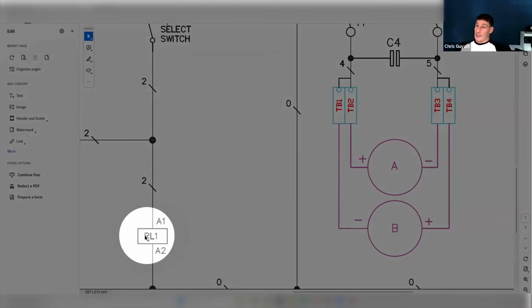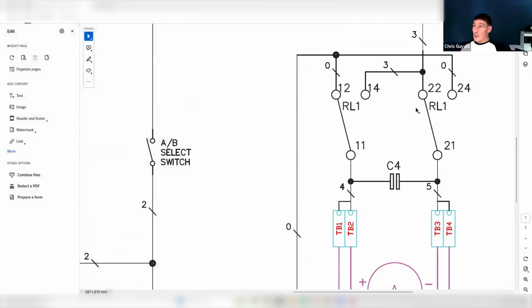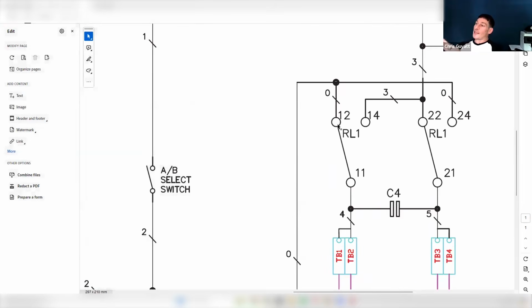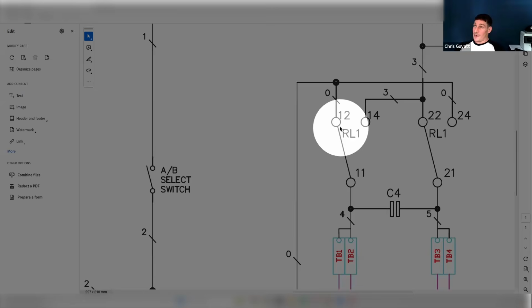Now we're energizing this relay, which switches the state. So now, because it's energized, this contact switches over to 14. It stays in this common, 11 and 21 are the common. So it switches, stays here, but switches over to 14 from 12, and the same thing, 22 to 24.